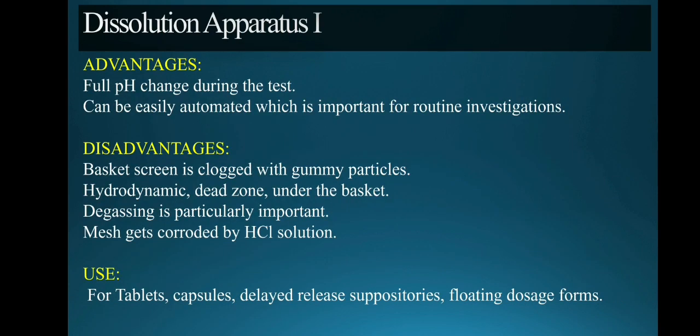Its advantages include that fluid pH changes are possible during the testing, and it can easily be automated. Its disadvantages include that, as we are using a basket, there are chances that it may get clogged with gummy materials. There are possibilities that a hydrodynamic dead zone is created under the basket. Degassing is a particularly important step, and the mesh gets corroded by the HCl solution, as we are mimicking the condition of the stomach. The uses of the apparatus include tablets, capsules, delayed release suppositories, and floating dosage forms.